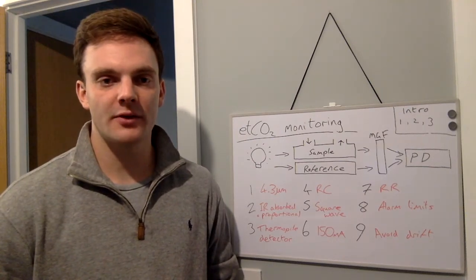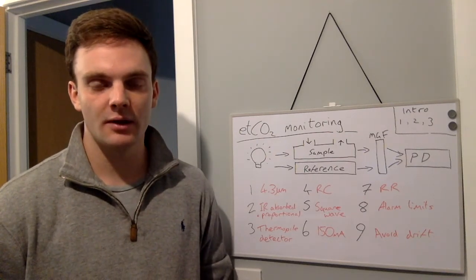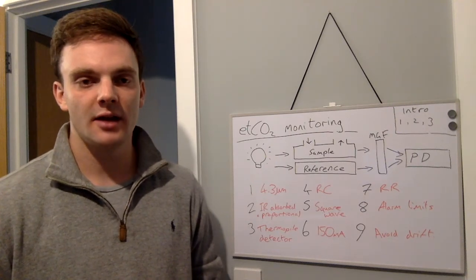We can set alarm limits on the monitor for high and low values of end tidal CO2, and the analysers should be regularly calibrated in order to avoid drift.